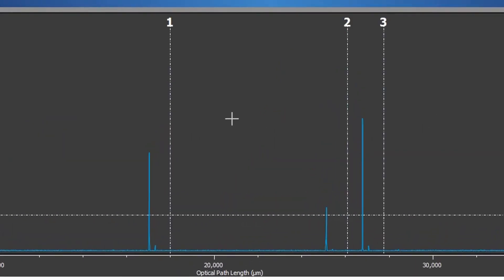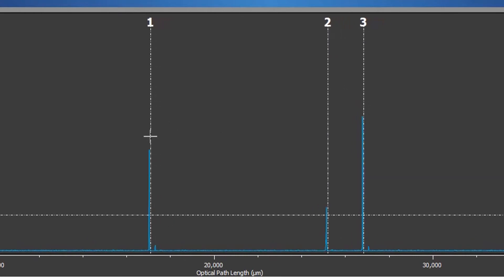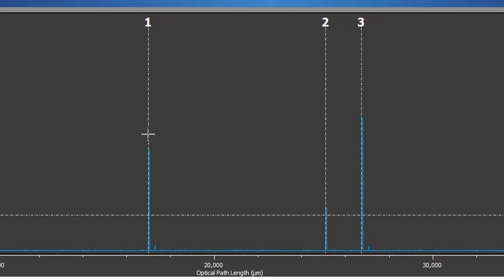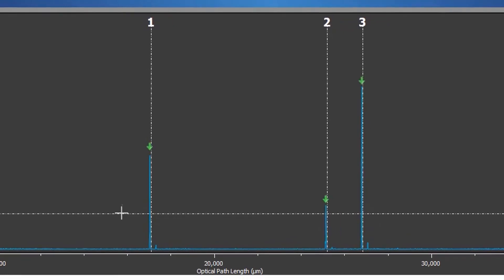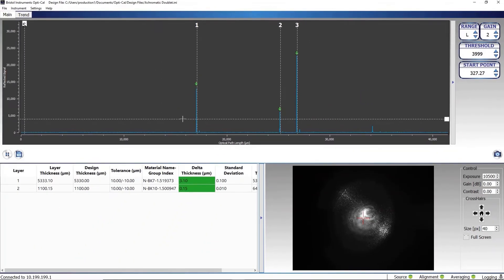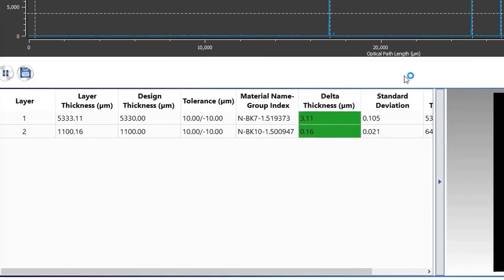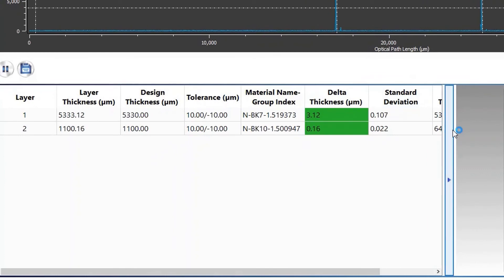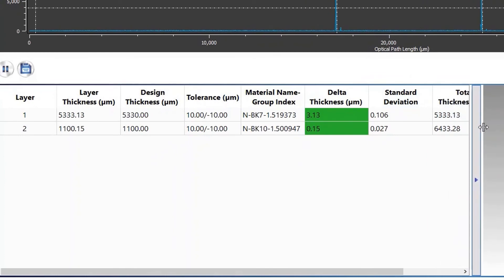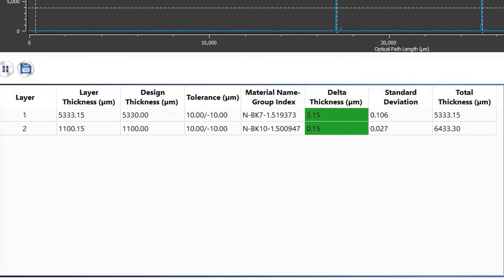The one, two, and three numbered lines represent the design thickness of the doublet. Using a mouse, we drag the design indicators over the actual measured elements. The display now shows that both elements are within the design tolerance of 10 microns.